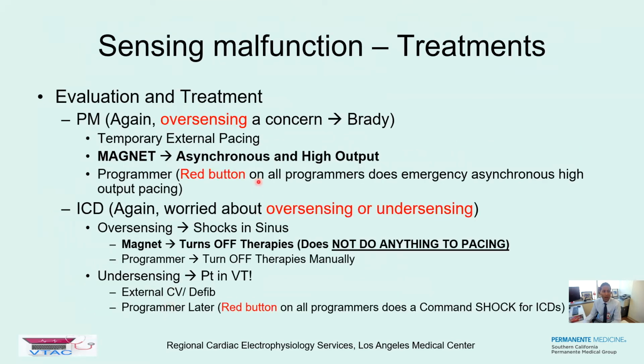So what's the treatment? Like Dr. Gupta said, save that for an EP lecture - what's the practical treatment? I think this one is probably the take-home slide. A magnet - you see magnet on both. Usually a magnet will take care of both things, right? Because if it's oversensing, a magnet will change it to asynchronous and start to pace. And if it's oversensing on an ICD, it will turn off sensing and turn off therapies. Now, the important point is that it does nothing to pacing on an ICD, so they could still end up having asystole from oversensing, and at that point you have to grab the programmer.